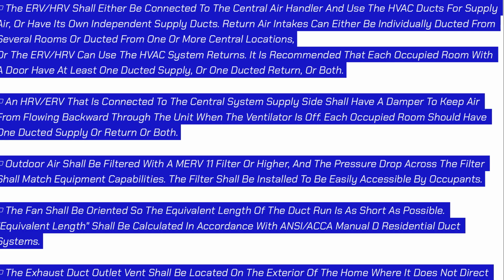Outdoor air shall be filtered with a MERV 11 filter or higher, and the pressure drop across the filter shall match equipment capabilities. The filter shall be installed to be easily accessible by occupants. The fan shall be oriented so the equivalent length of the duct run is as short as possible. Equivalent length shall be calculated in accordance with ANSI, ACCA Manual D, Residential duct systems.